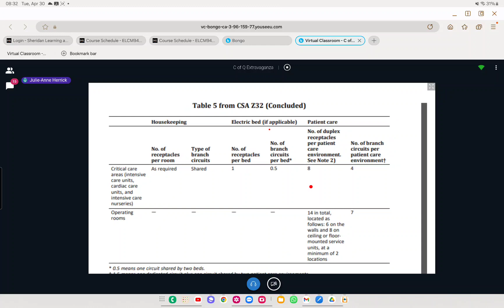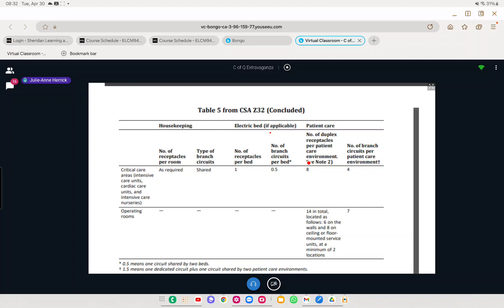Branch circuits per bed, 0.5. But notice the little asterisk: 0.5 means one circuit shared by 2 beds. Number of duplex receptacles per patient care area, 8, again with note 2. So if you get a question about patient care areas and receptacles, you don't have to read the code, just look for the table. It already does it for you.